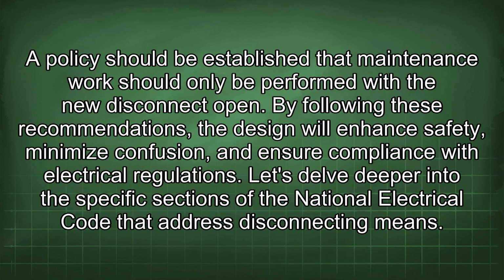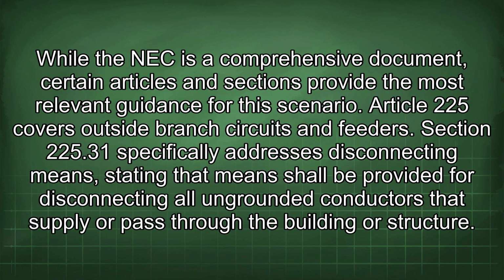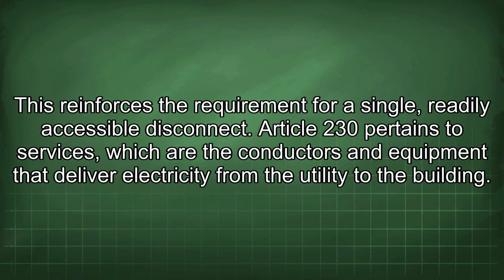Let's delve deeper into the specific sections of the National Electrical Code that address disconnecting means. While the NEC is a comprehensive document, certain articles and sections provide the most relevant guidance for this scenario. Article 225 covers outside branch circuits and feeders. Section 225.31 specifically addresses disconnecting means, stating that means shall be provided for disconnecting all ungrounded conductors that supply or pass through the building or structure. This reinforces the requirement for a single, readily accessible disconnect.